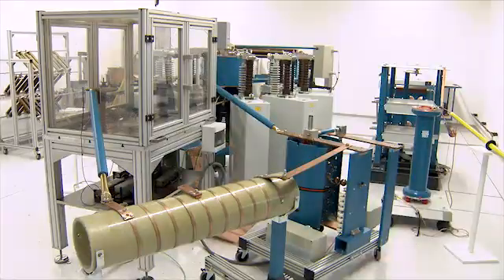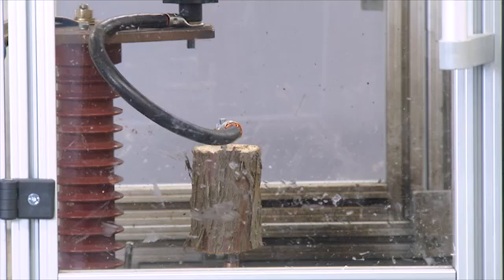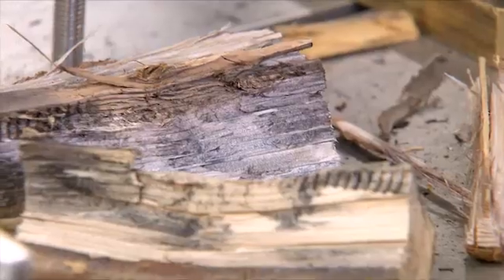We can simulate lightning currents and surge currents of 100,000 or 200,000 amps, and that is on a realistic network capable of driving a short circuit current to the test object of up to 50,000 amps.